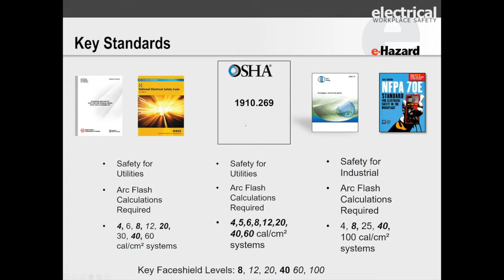Some general principles: melting and flammability are the most dangerous. Unfortunately, in Canada, there's a standard being used a lot right now called ASTM F2302. That standard has now been withdrawn from ASTM because it did allow melting materials to be called flame resistant. These materials are quite dangerous. You want to use the standards actually cited in 70E or Z462.